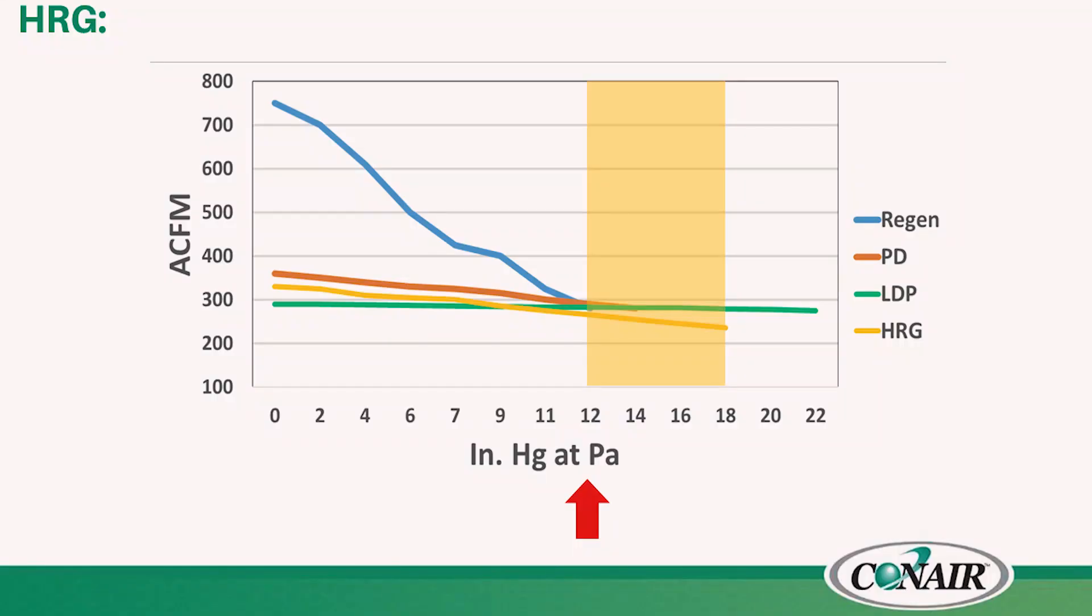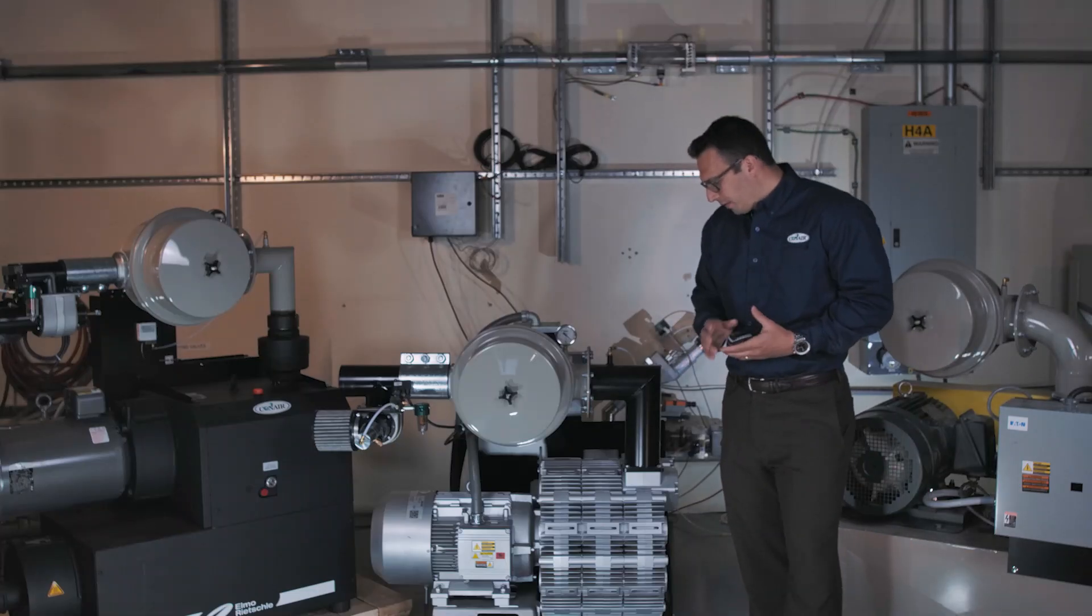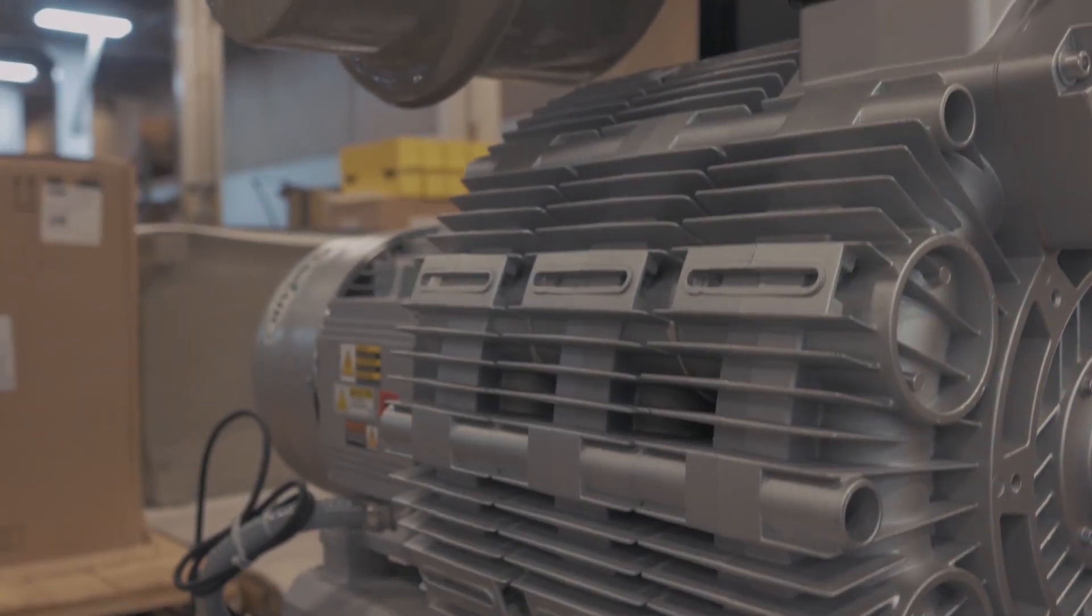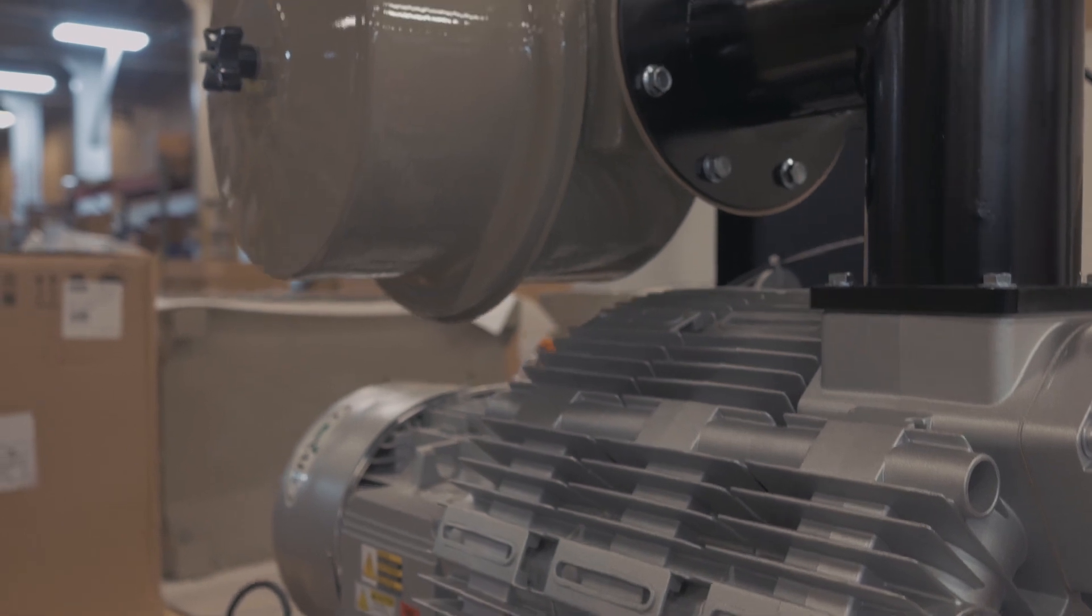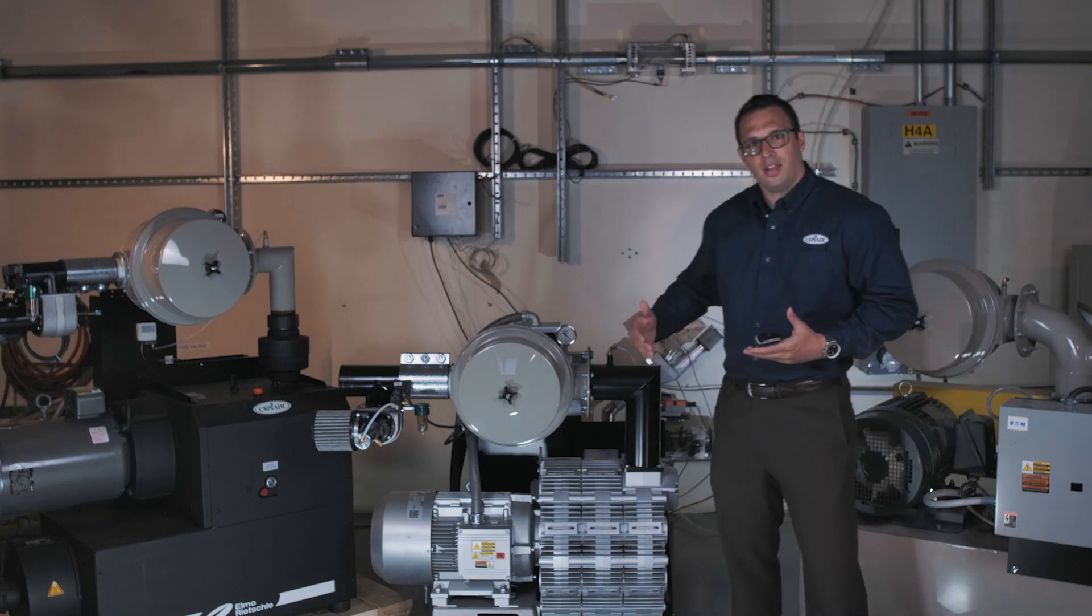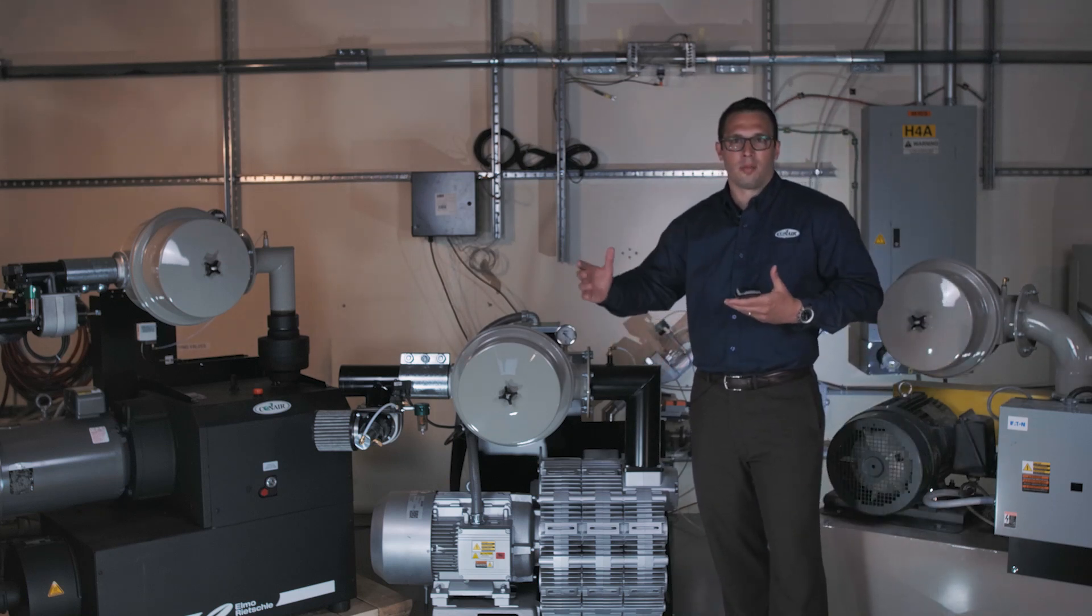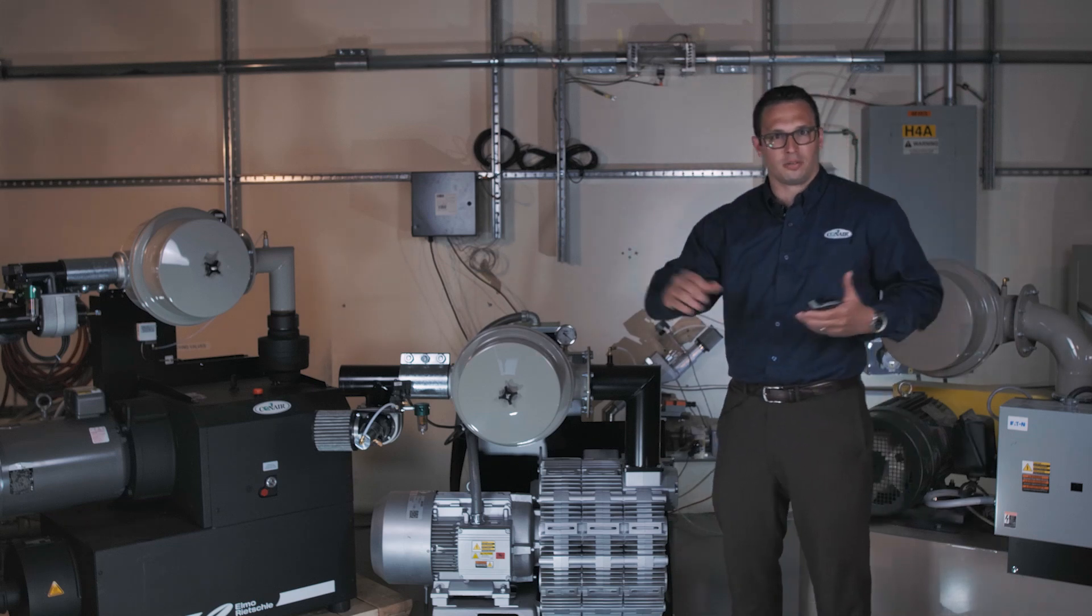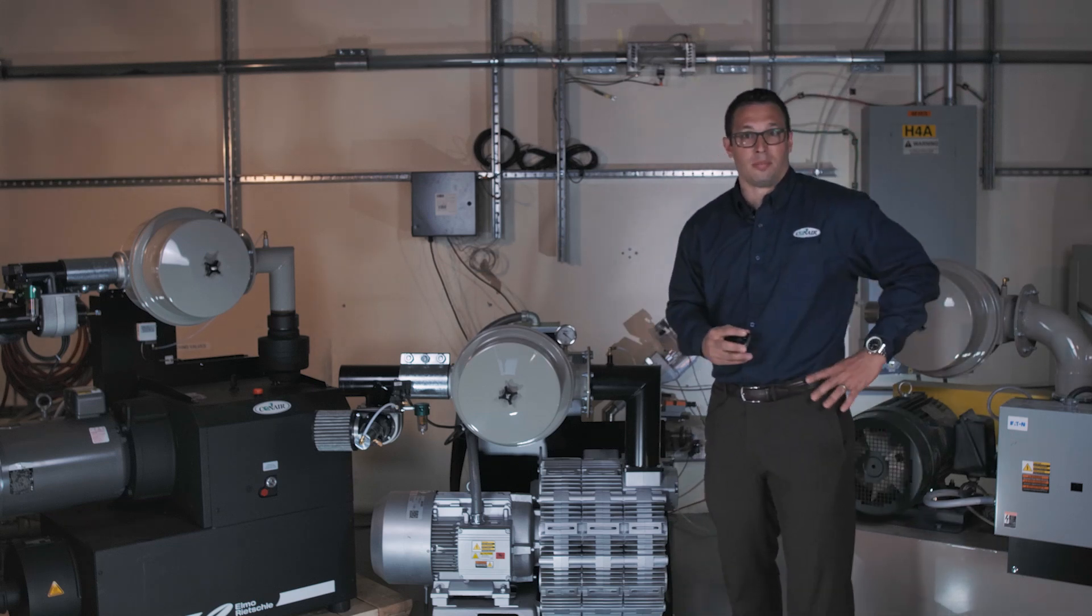I've just put up on the screen a new pump curve that now shows our HRG pump that Conair recently released to the market. This is the pump that we have here. It's a triple stage regenerative pump. And what those triple stages allow us to do is achieve much higher vacuum than what a typical regen or positive displacement pump is capable of. That also adjusts how the pump operates and how the pump curve looks with respect to the full spectrum of vacuum that it's capable of.